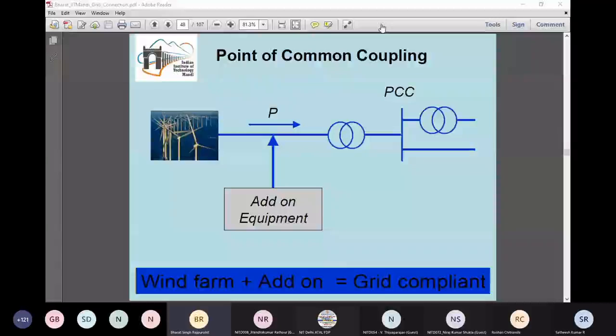Fine. So it means active power is available with the wind farm or wind turbine, but if the frequency of the system is going beyond the range, then to maintain the grid frequency in a specified range, the output of a wind farm should be reduced. We are not increasing the power, but we are reducing the power which is available with the wind farm, to maintain the grid frequency. So this is my answer. If it is not clear, then can you please once again raise your query?